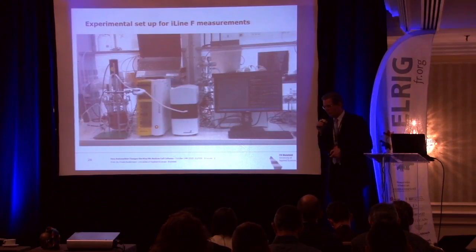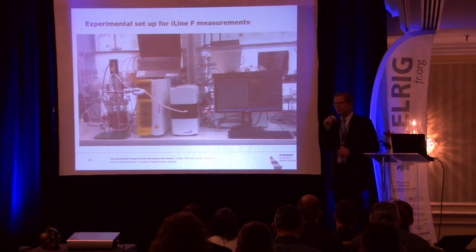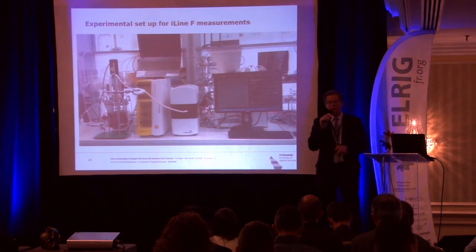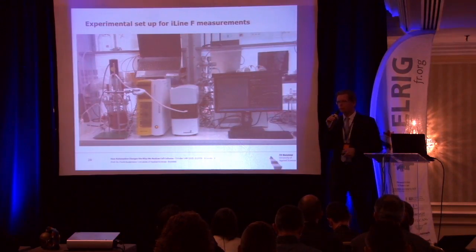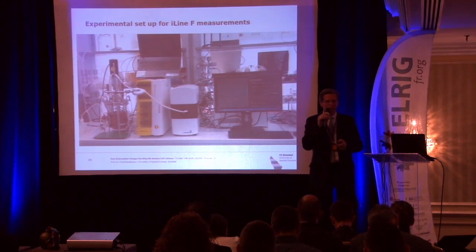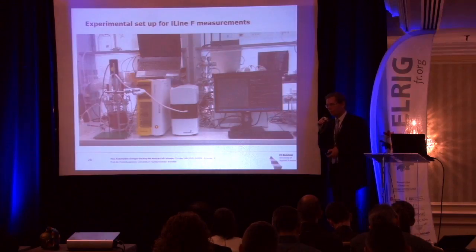So this is the actual system working in the lab. And as you can see here, this is the holographic part of the hardware. And then there is a line going into the bioreactor to get the sample out. But the fact that it is not necessary to use trypan blue allows this principle to bring the cell sample back into the bioreactor after the hologram has been generated. And that, of course, puts the samples back in the bioreactor, and you don't lose any sample volume.